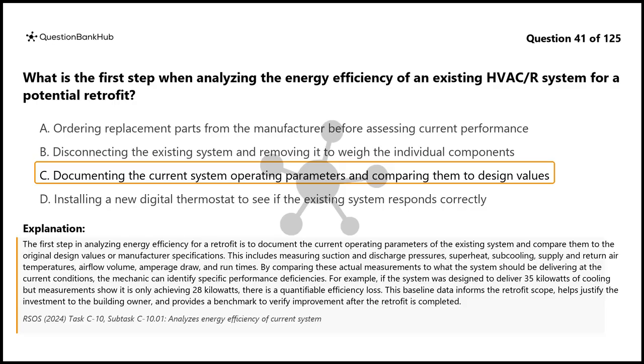By comparing these actual measurements to what the system should be delivering at the current conditions, the mechanic can identify specific performance deficiencies. For example, if the system was designed to deliver 35 kilowatts of cooling but measurements show it is only achieving 28 kilowatts, there is a quantifiable efficiency loss. This baseline data informs the retrofit scope, helps justify the investment to the building owner, and provides a benchmark to verify improvement after the retrofit is completed.